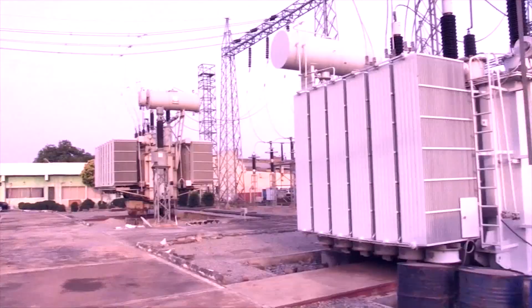Delivering critical infrastructure ahead of its time is a prime objective at the Transmission Company of Nigeria (TCN). To this end, the company has almost completed a mega transmission substation in the Lugbe area of Abuja. TCN deployed a hybrid technology comprising air-insulated substation (AIS) and gas-insulated substation (GIS) to build the 330, 132, 33 kV Lugbe West main transmission substation in Abuja. This game changer, upon completion this year, will revolutionize the bulk electricity supply of the axis it will serve. Tag along for the details.